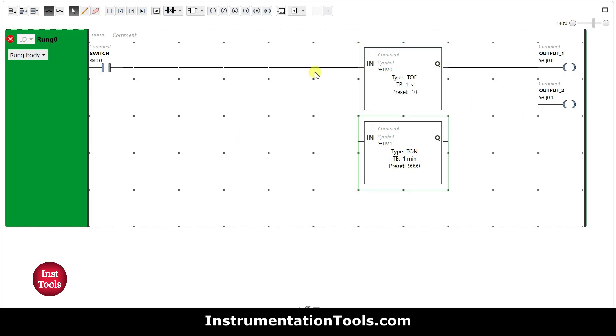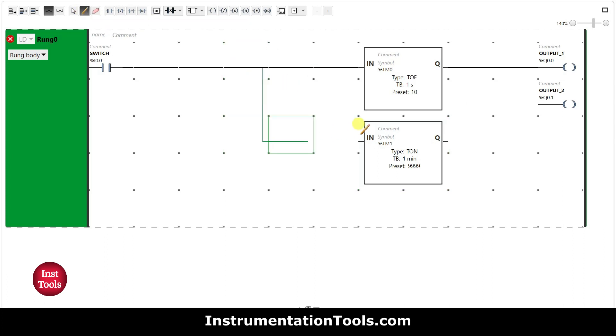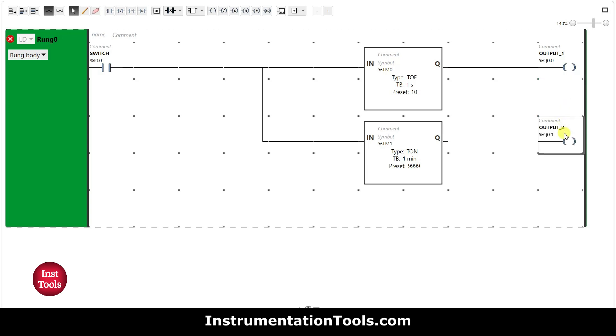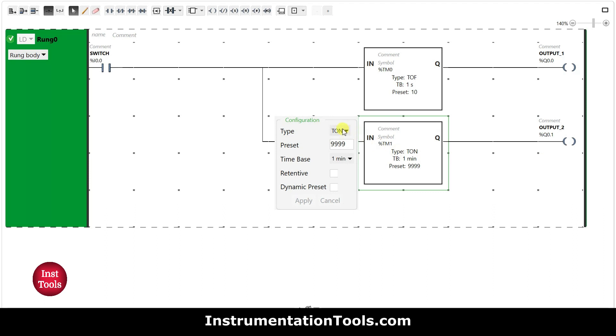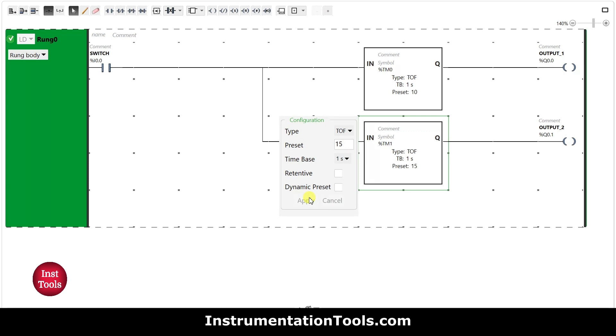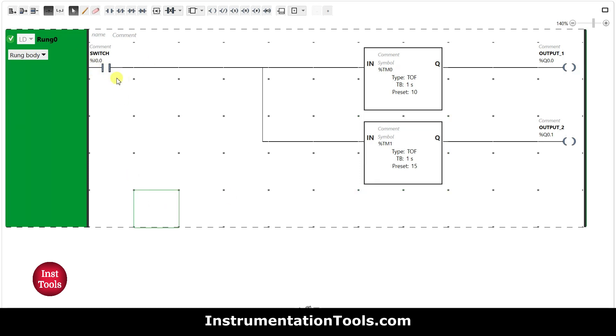For output 2, I will connect the timer and set it to T-OFF, change the time base to 1 second, and set the preset value to 15, then click Apply. So when the switch is turned on, output 1 and output 2 will be on, and when switch is turned off, output 1 will turn off after 10 seconds and output 2 after 15 seconds.